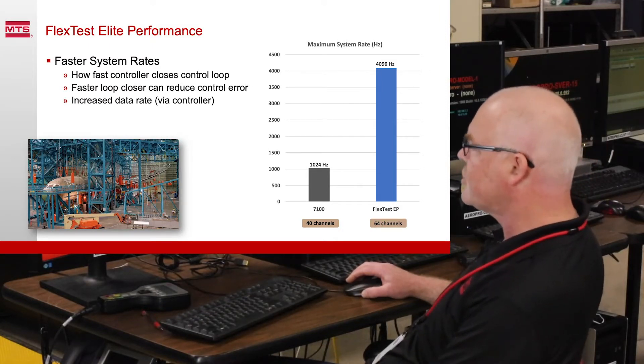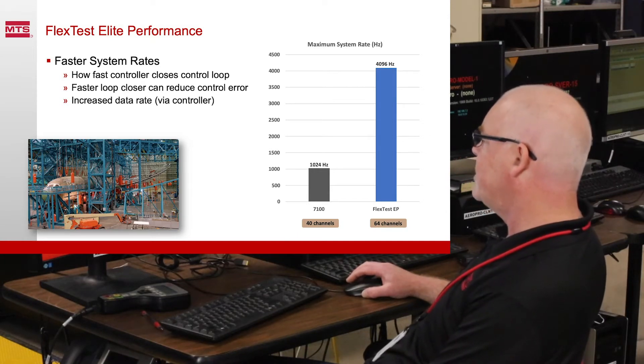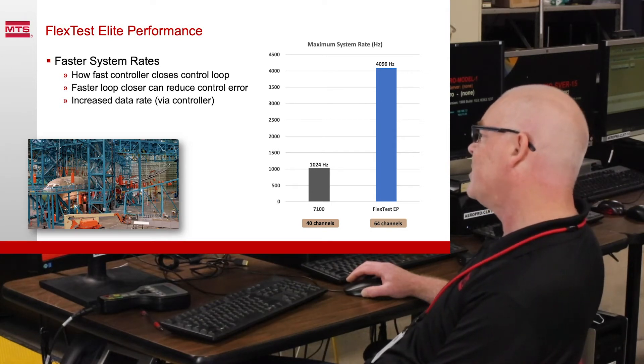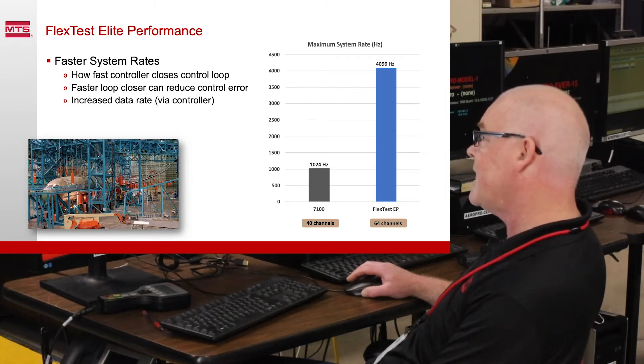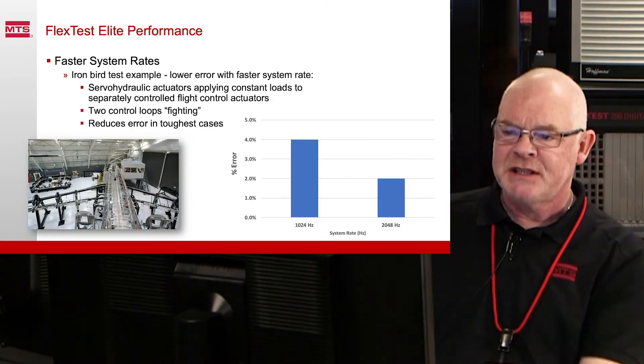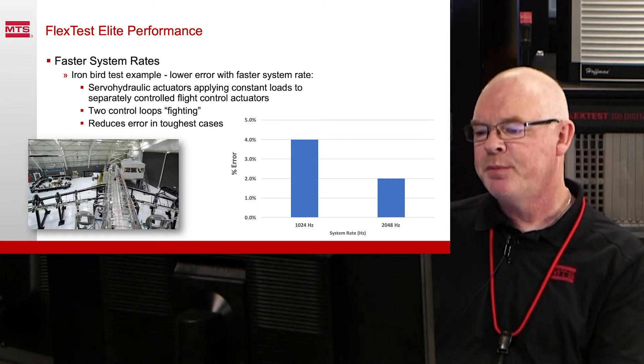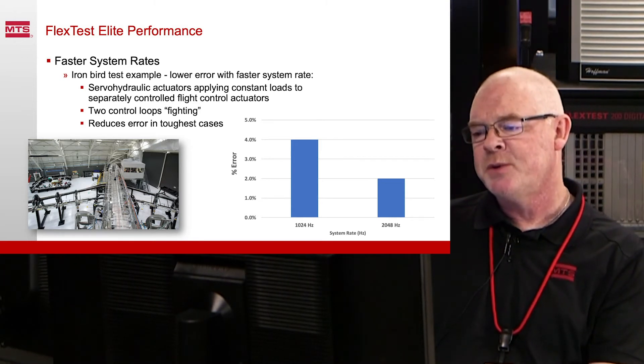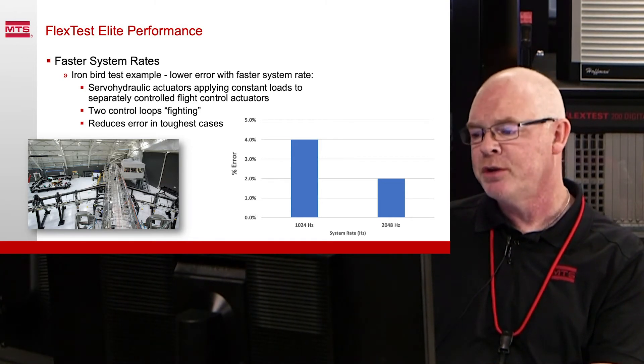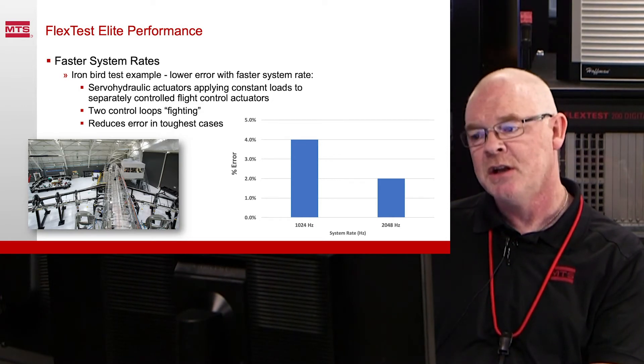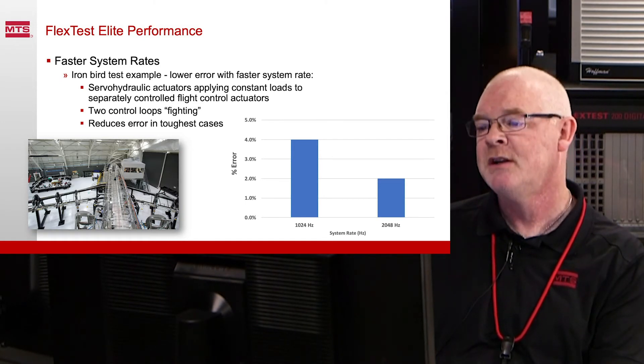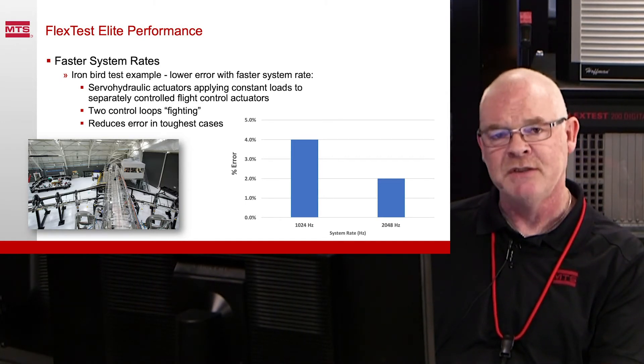Another benefit is faster system rates — that's how fast we can close the control loop. Faster loop closure can reduce controller error and increase data density from the control system, since the maximum control loop rate determines the maximum rate of data out of the box. Faster system rates improve the error experience through testing; we're making adjustments to the control loop at 2048 Hz rather than the standard 1024 Hz on the 7100 processor, giving an immediate increase in test accuracy.